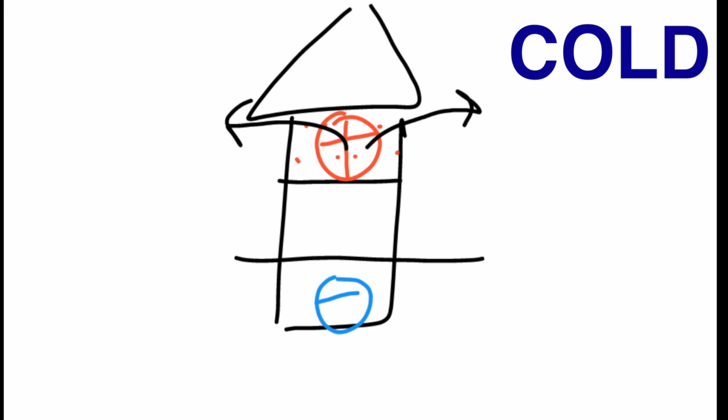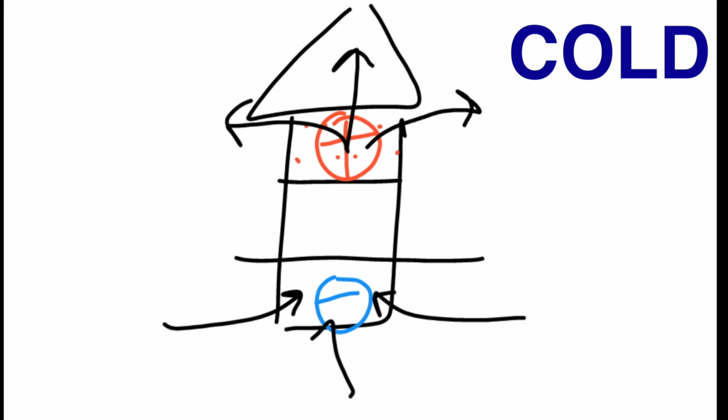And that is also leading to an infiltration on the bottom, that the high pressure pushes the air out the top, but also creates this vacuum and sucks the air in, much like a straw, on the bottom floors and through the cracks and the crevices of the buildings. So imagine a really tall building where that pressure gets really high at the top and really low at the bottom, and you have a lot of air circulation from the internal envelope to the external. So that's called the stack effect.